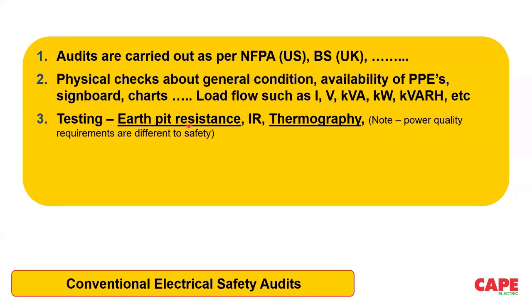Also, I put underline 2 things: the earth pit resistance measurement and thermography. Please note that the earth pit resistance measurement has been removed from the low voltage electrical safety standards a few decades back internationally, and even in the IS 732, if you look at the 10 testings, the earth pit resistance measurement is not mandatory. The technology has already changed, not now, 20 years back. Similarly, thermography is not a recognized test or recognized verification mechanism in the standard, which I have shown you earlier. Thermography, of course, for solar PV, yes, you can do that. But for an electrical installation inside a building, thermography is not recognized until now.